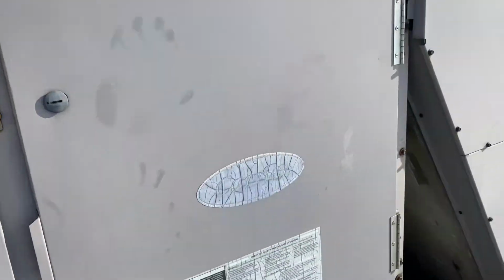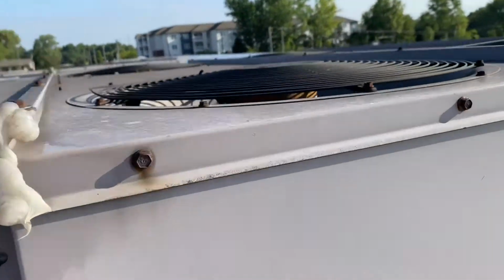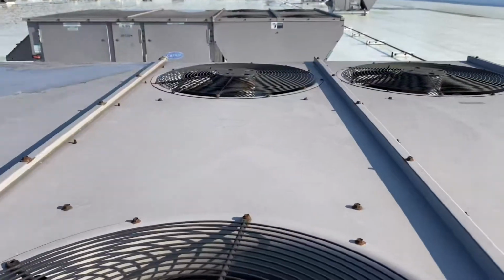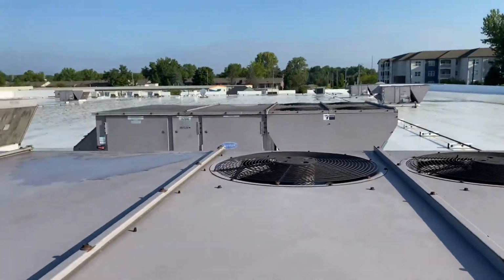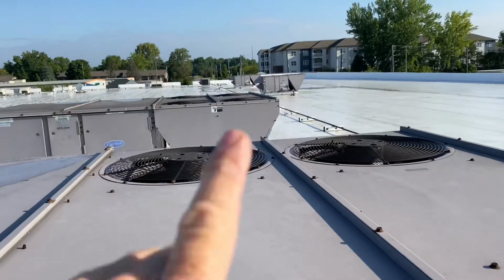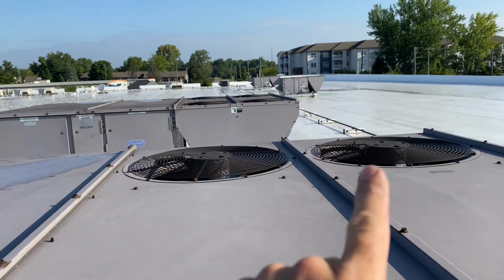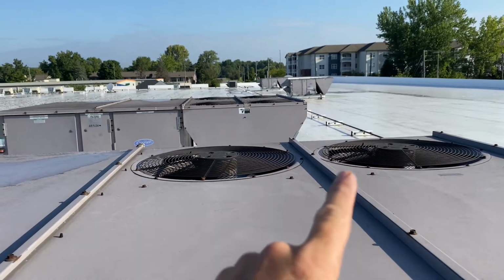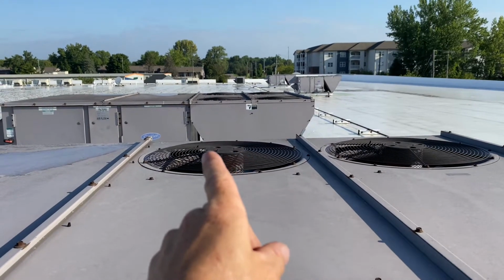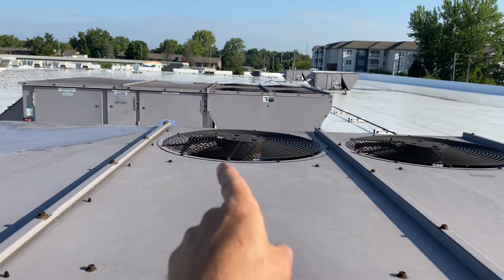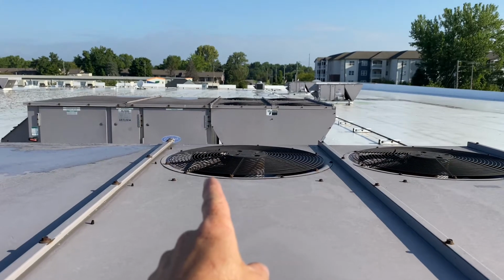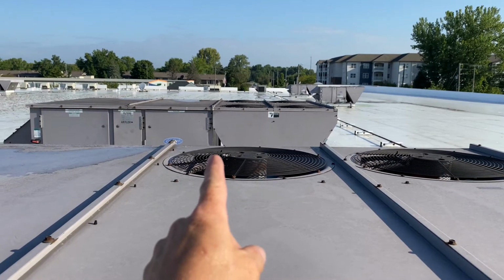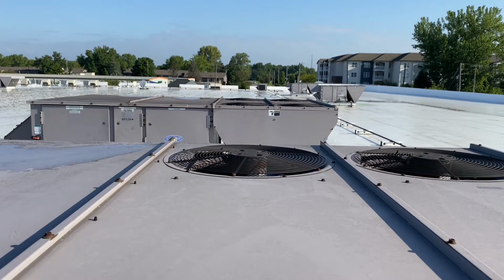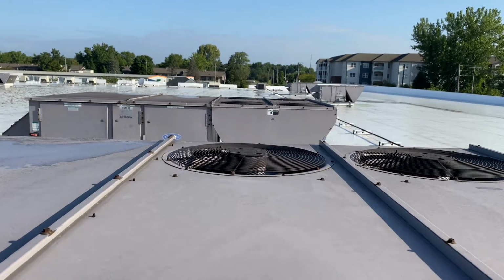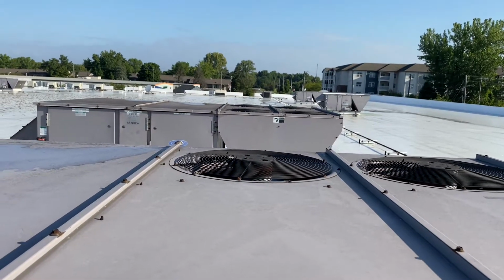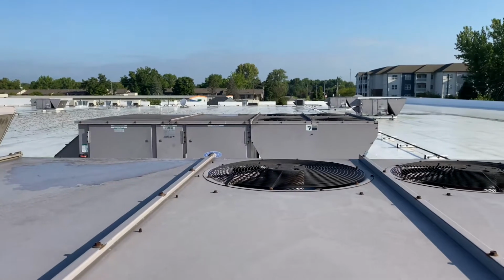They cycled on. I came up over here quick enough to watch the fans, just to peek up here, and they were both running. These two were running, which makes these 2 and 3. And as soon as I popped up here, I saw a spark come from right about here or so, and then it popped the fuse, killed the fans, so killed 24-volt power again.